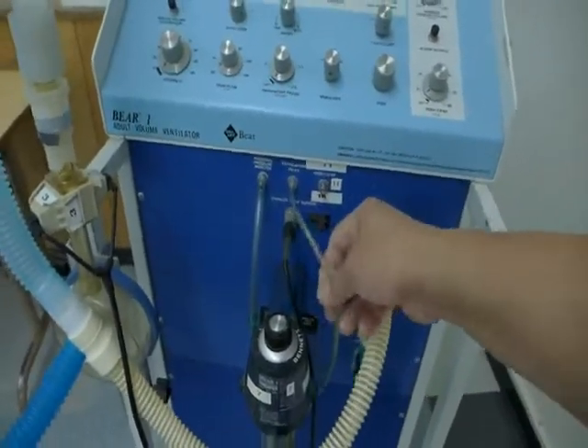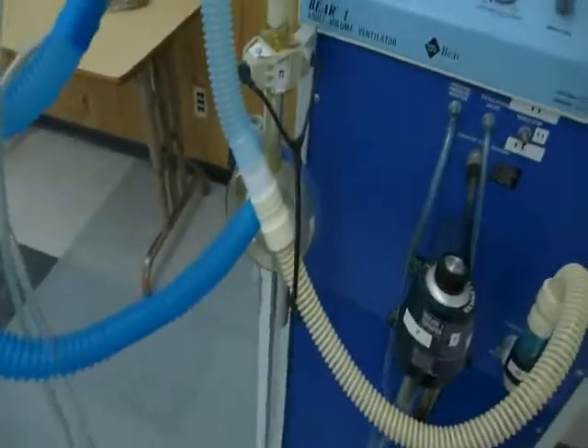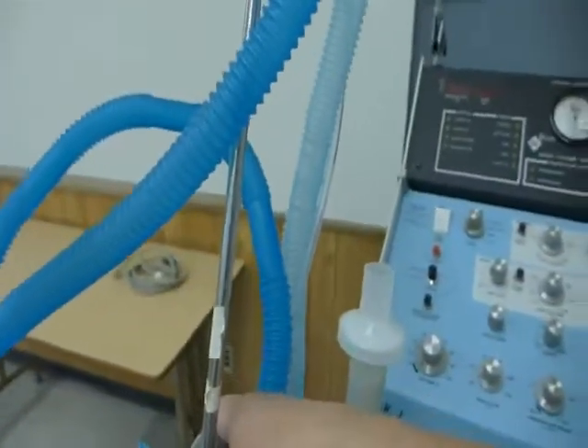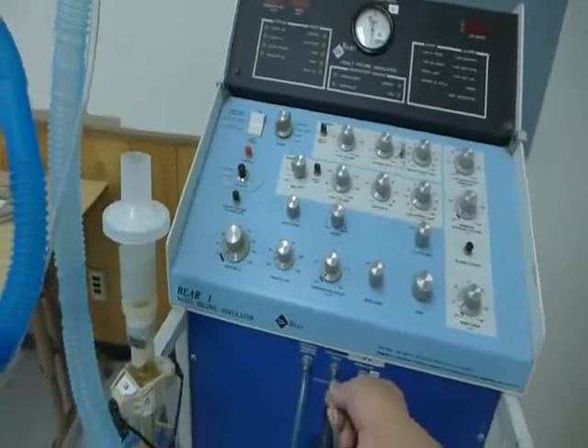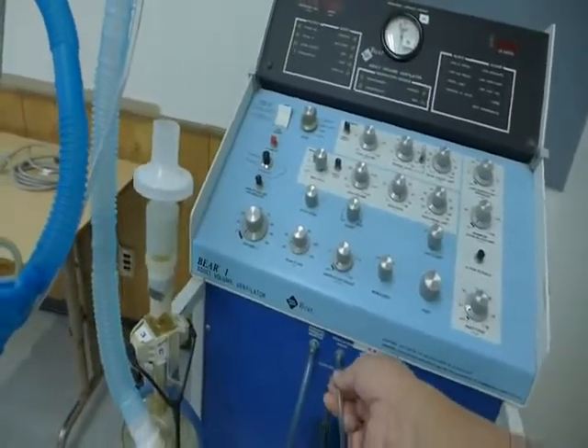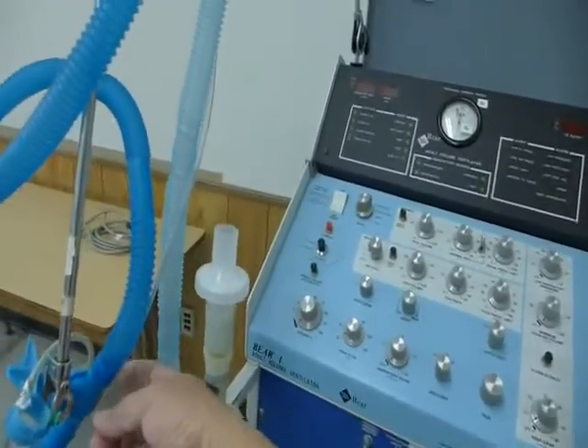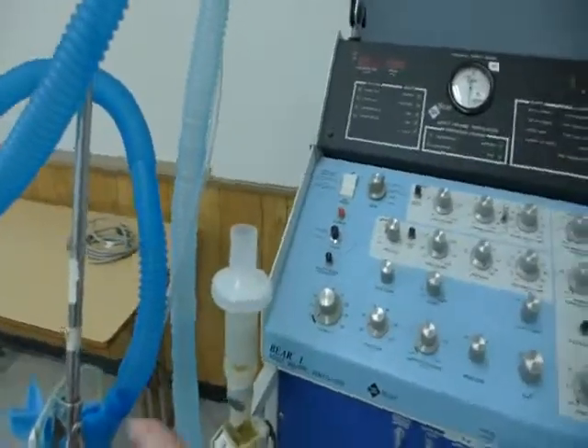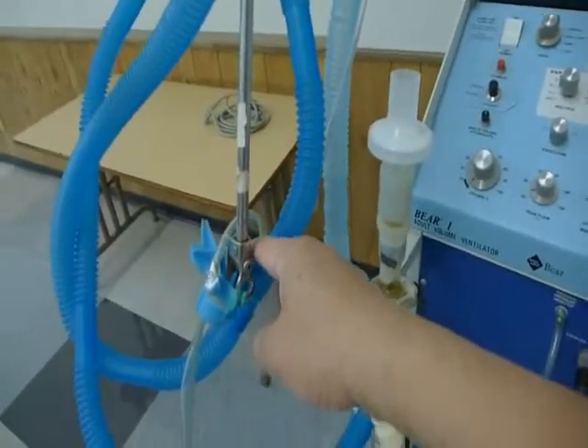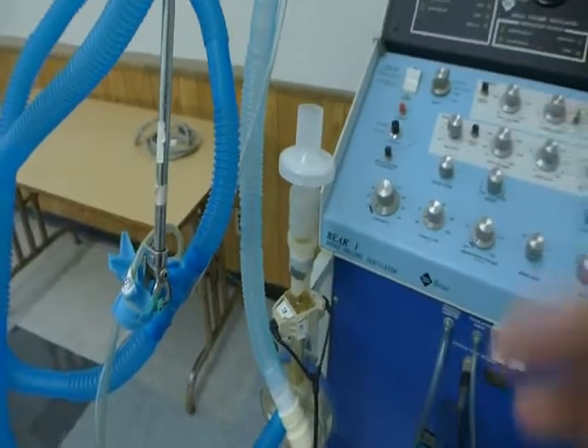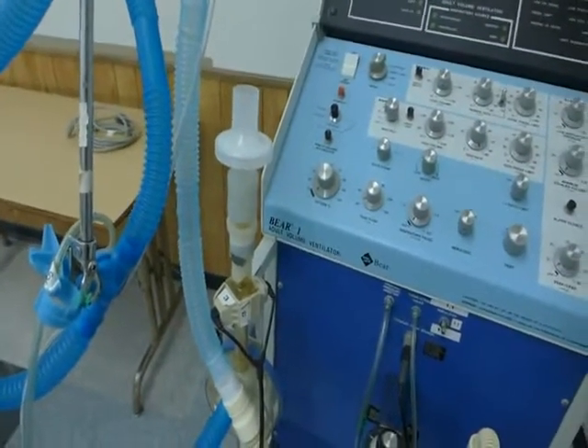And then we have the exhalation valve. This tubing here is connected to the back of the exhalation valve. It has a driving mechanism back there to activate the exhalation valve, turning it on and off during inspiration or expiration.